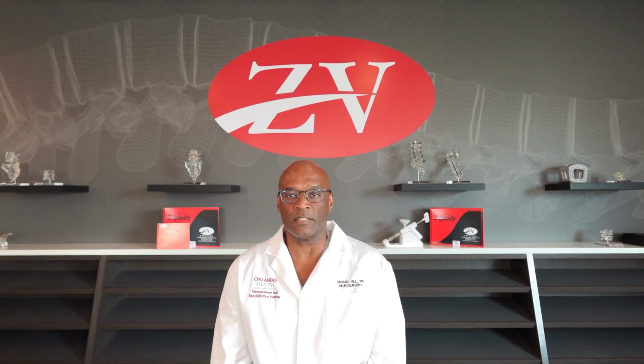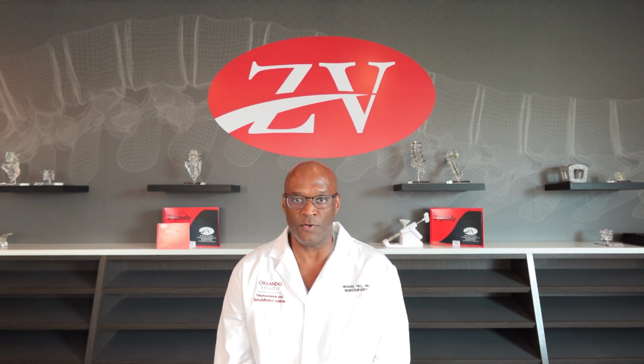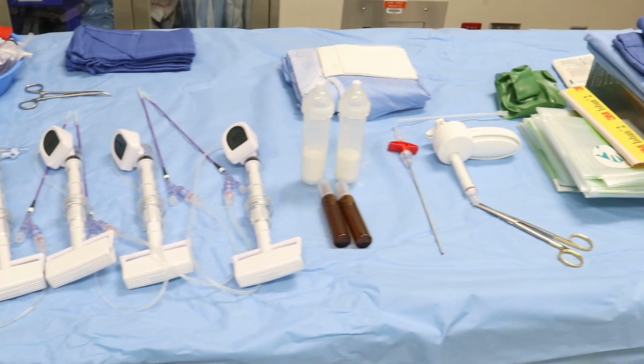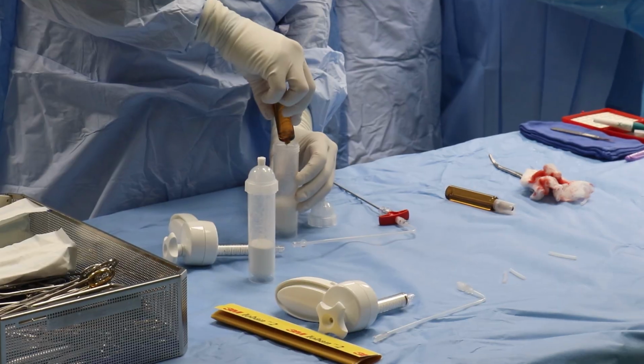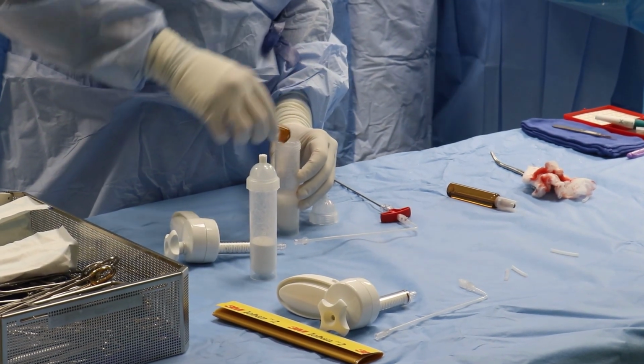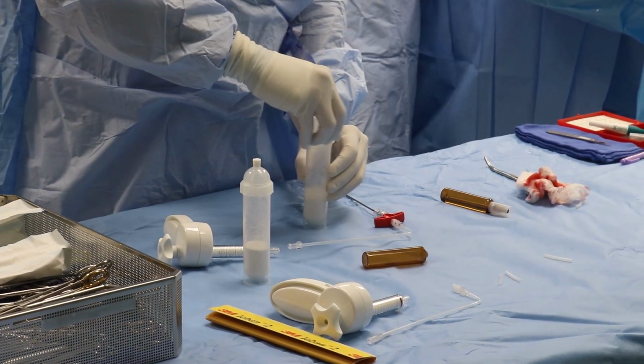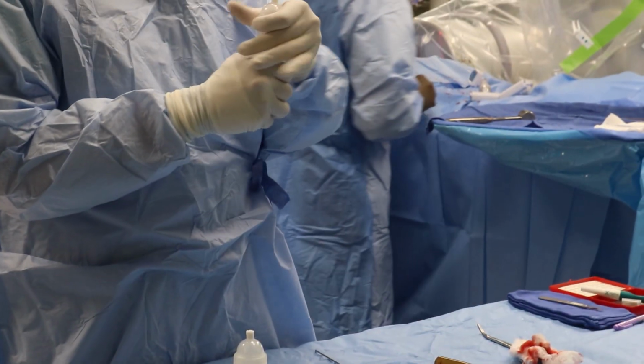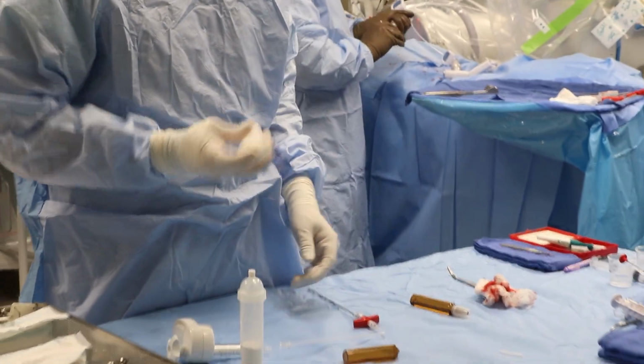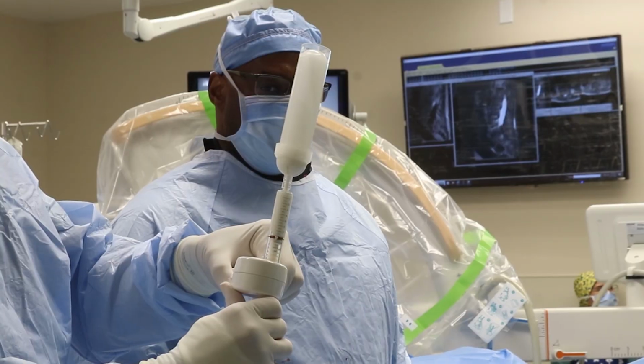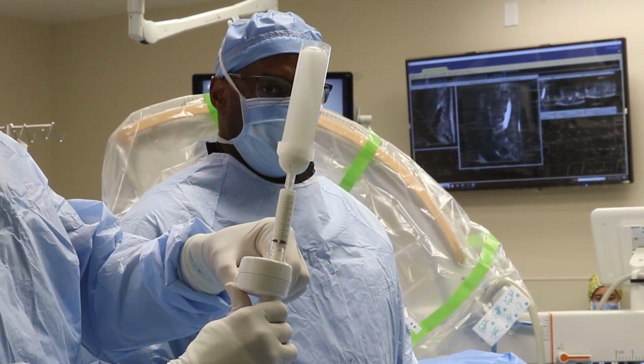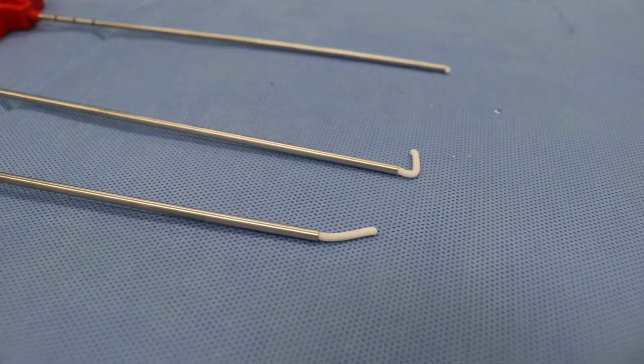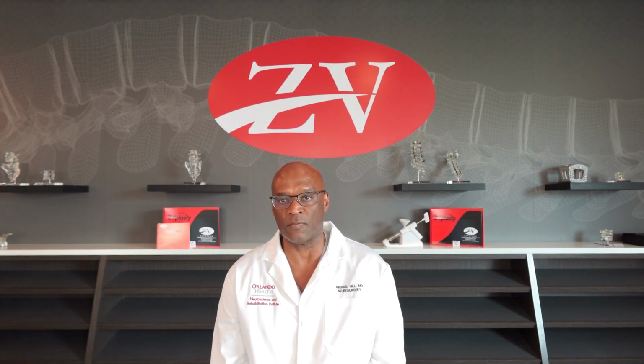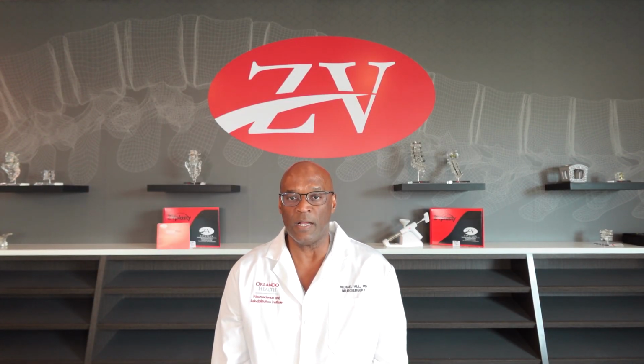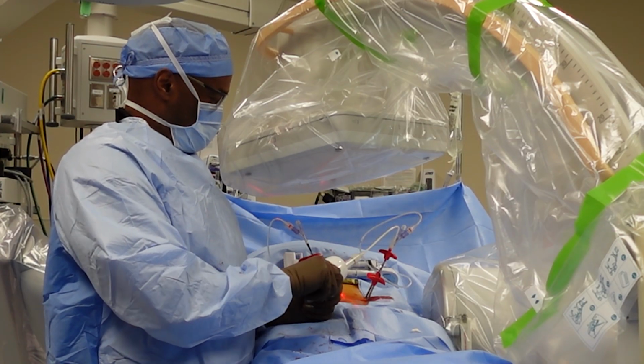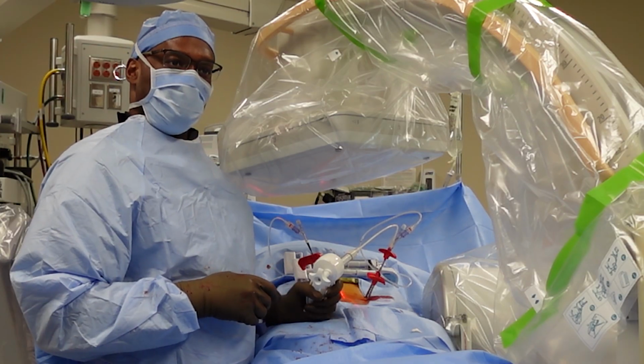In mixing the OsteoFlex for your use through doing the Zavation ZVplasty procedure, they give you a number of different options in the technology that allows you to have very consistent delivery of the cement. Mixing time is simple with a 15-second mixing. It allows you to have a long working time for the cement, which is about 20 minutes, and it allows you to infuse the cement in a very controlled delivery fashion.